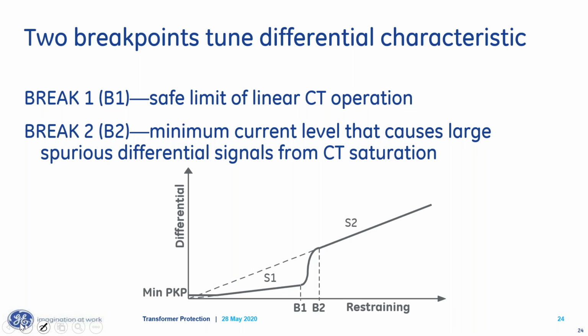Now, the real question you asked was, what should you set the slopes to? Again, this is not going to be a scientific discussion, especially at the lower slope, because we have to make some guesses, some calls, right? So the first thing is we want to set that lower slope so that we accommodate error in the steady state. If we're in the linear portion of the CT saturation curve, we can have 10% error. So I never want to set that below 10%. On top of that, I could have some error because I've got some remnants stored inside of my CT, right? It may have had some remaining magnetism in it. Because of that, I'd add another 10%. So now I'm at 20% before I set my minimum slope.